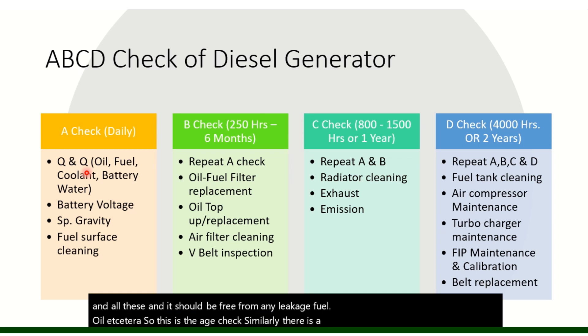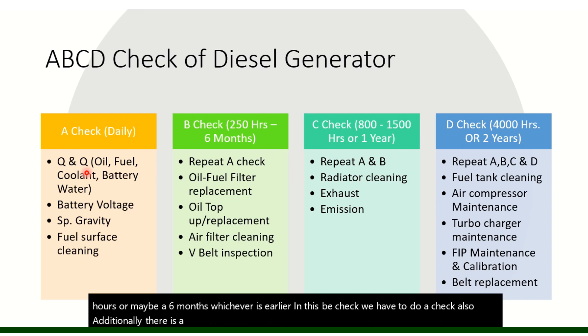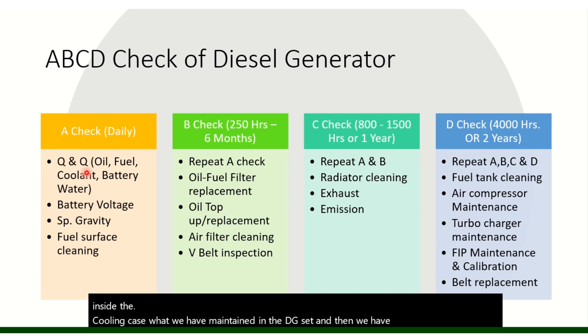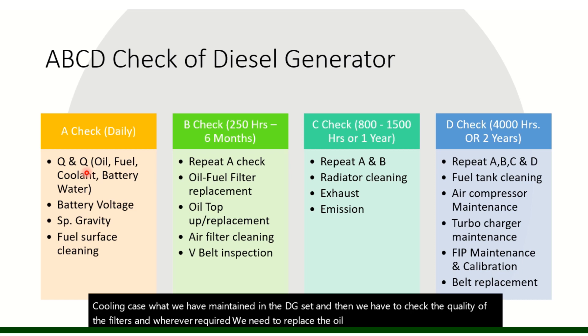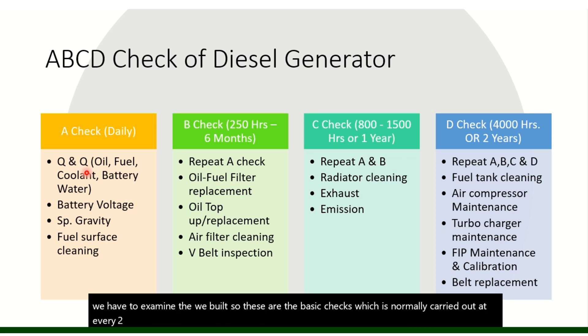The B Check is performed every 250 hours or six months, whichever is earlier. In addition to the A Check, it includes replacement and top-up of engine oil and water coolant in the cooling system. We also check the quality of filters and replace the oil filter, fuel filters, and air filters where required. The V-belts are also examined. These are the basic checks carried out at every 250 hours of DG operation or six months, whichever is earlier.